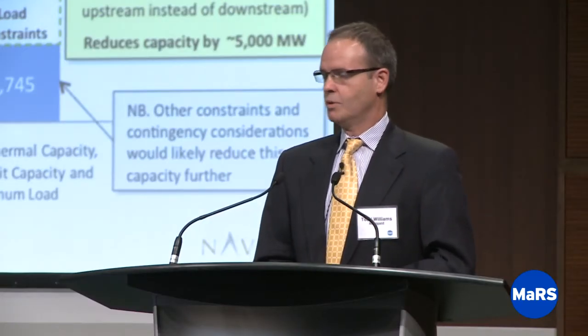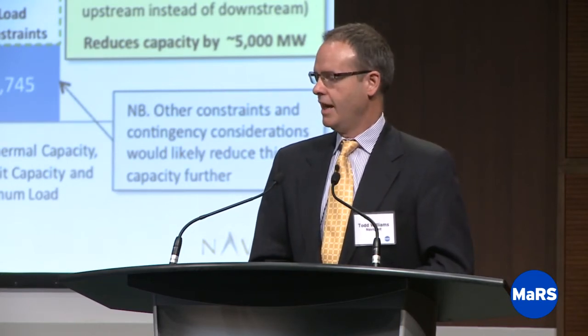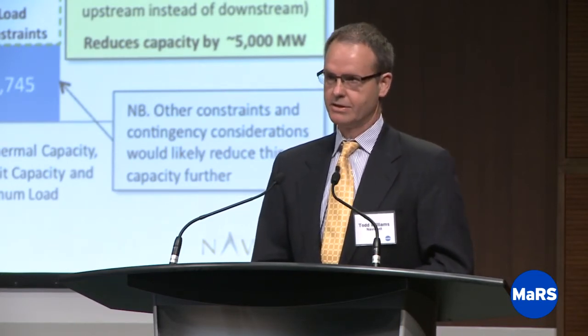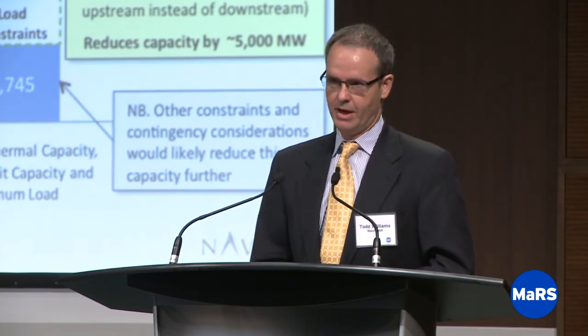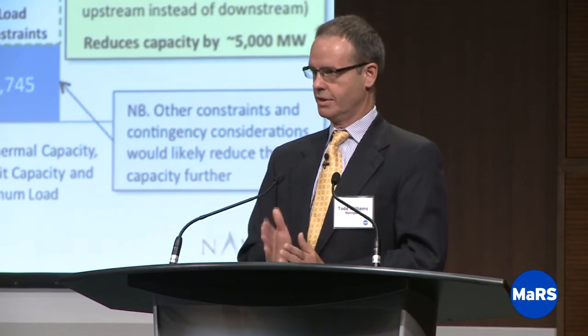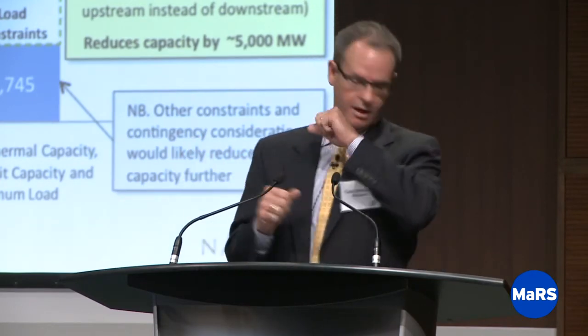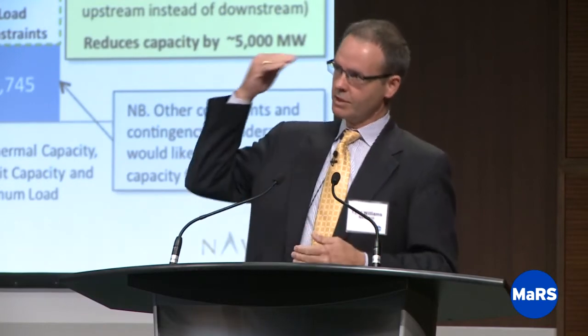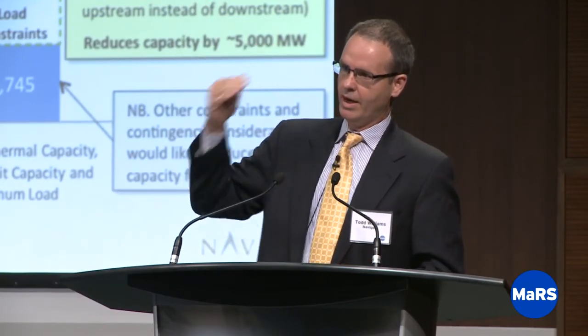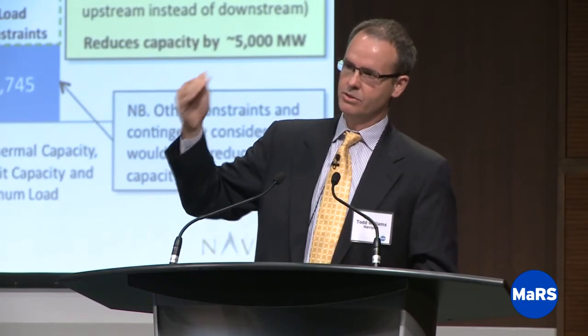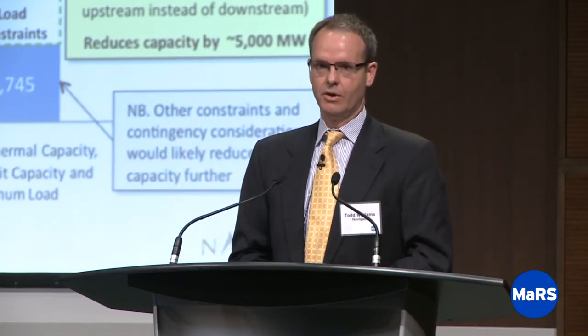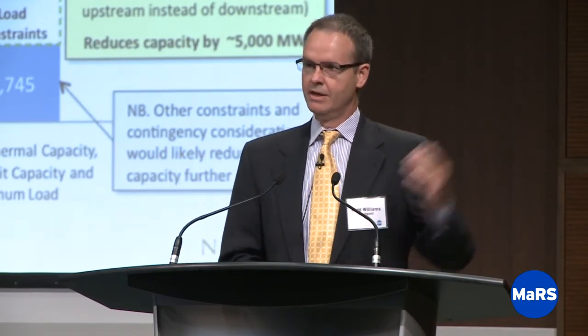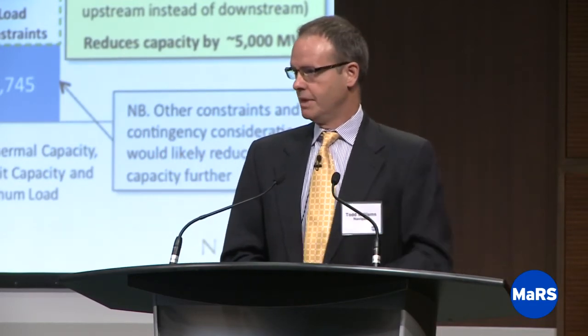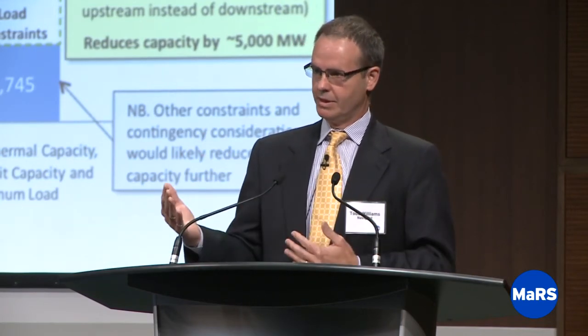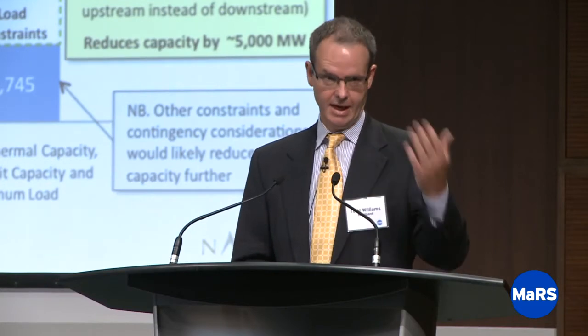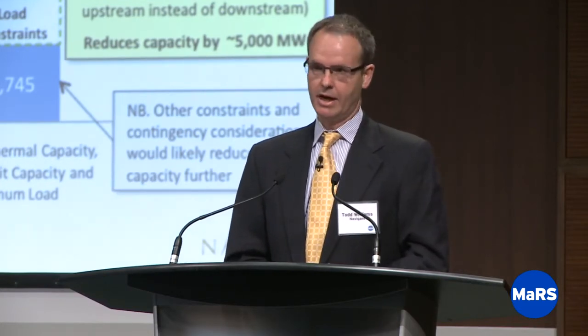I want to point out this was a relatively simplistic analysis. There are probably other factors, contingencies and constraints, that reduce that 4,000 even more. But I wanted to show you the sequence of steps. If you're sitting in this building and asked how much you could connect on the roof, you'd look upstream in the network and ask what the most constraining factor is. In this building it could be short circuit, I suspect it would be. Somewhere else, in rural Ontario, it could be minimum load. It depends where you are and what the network looks like, but these are the constraints, and the reasons someone told you that you couldn't connect.